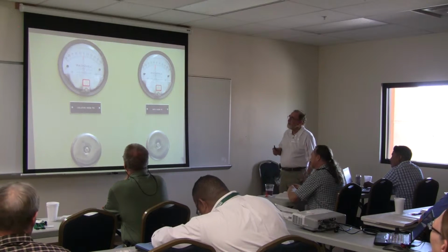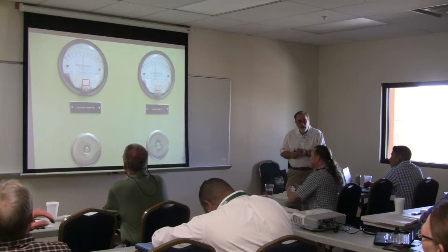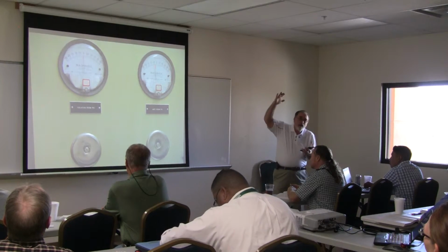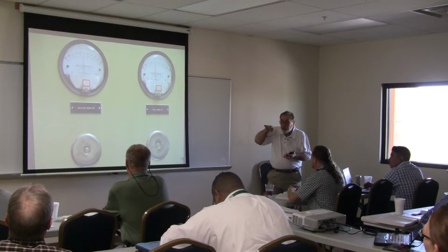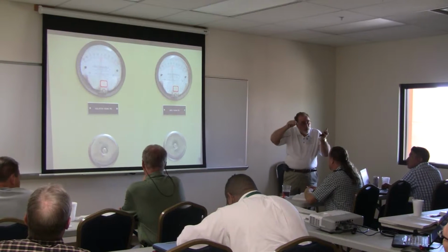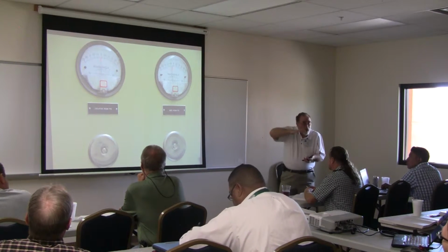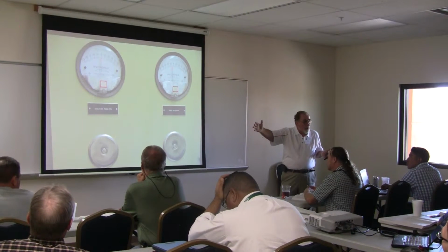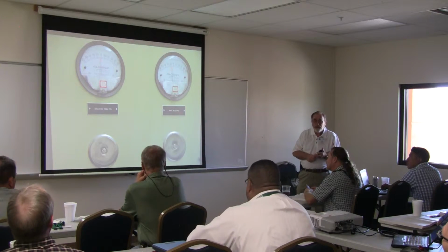So, anyway, the idea behind an isolation room is that rather than positive pressurization, in other words, what's happening is you're pushing air normally into a room like this, and then if you don't have a return air in the room, it's going out from underneath the door. So you're actually pressurizing that room and then pushing the return air out into the hallway in a lot of cases. But in this room, it's just the opposite.